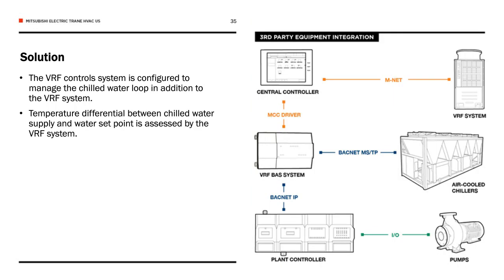In that scenario, VRF manufacturer provided controls and integration between all systems on that campus, including a plant controller, air-cooled chillers, pumps, and the VRF system going into the new facility and campus dorm. The VRF system was configured to manage the chilled water loop in addition to the VRF system, and the temperature differential between the water and supply water set point was assessed by the VRF system.